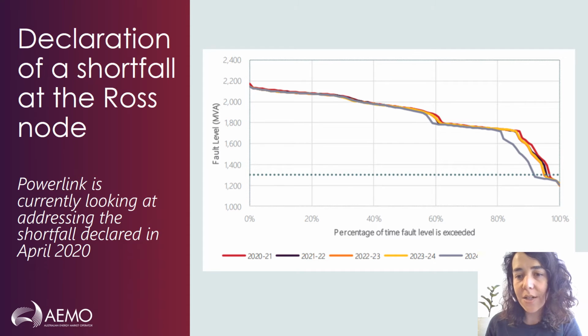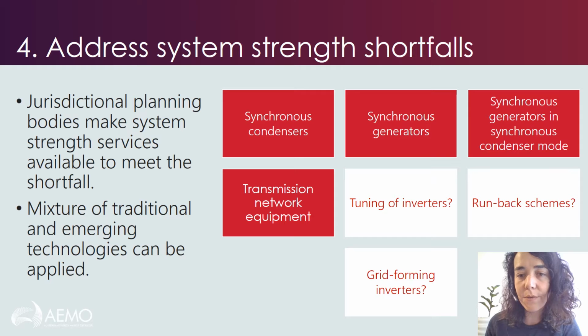Here you can see a representation that will often appear in some of our reports, our system strength reports anyway, showing the expected amount of time that we think that the fault level will be above the minimum requirement shown there in the dotted line across a year. And we project this for each of the 5 years in the 5-year outlook and look to see if there are situations, as you can see there in this Ross chart, where for a sufficient portion of time, we expect that we will not have enough fault level in order to declare a shortfall. Where you can see the lines there dipping below the minimum requirement, sufficiently worrying there for us to declare a shortfall. And we did in fact declare a shortfall at the Ross node in northern Queensland in April 2020, and PowerLink is currently looking at how best to address that shortfall.